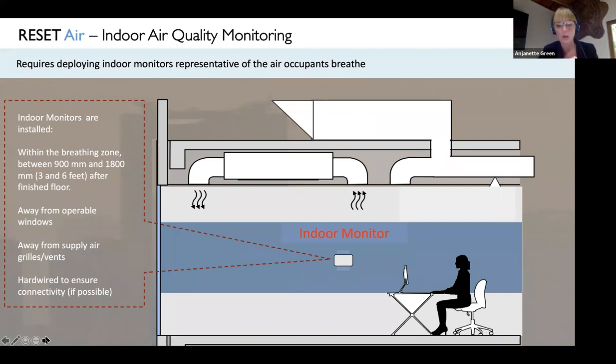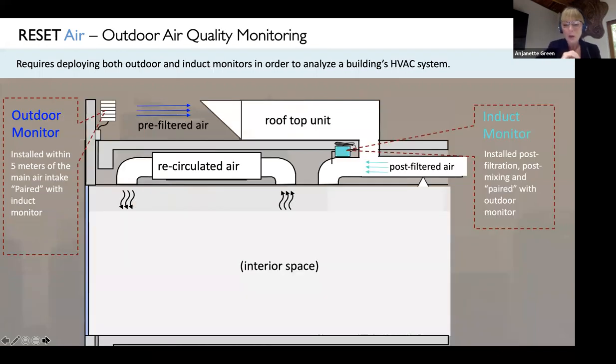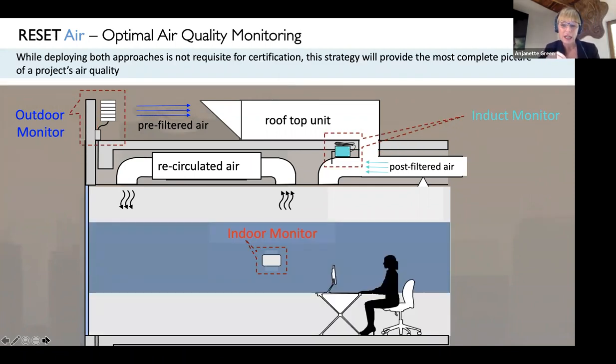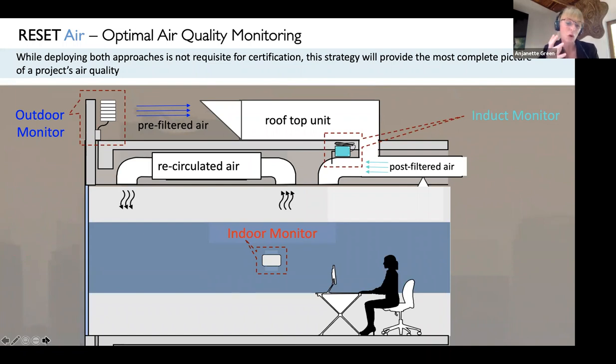The second approach is outdoor monitoring, which requires outdoor air quality monitors to set a baseline, plus in-duct monitors placed after filtration so a direct comparison can be derived. This performance determines if your HVAC system is doing what it should — filtering the air, mixing it properly, and delivering great air to occupants. Deploying both approaches enables you to decouple the data coming from indoor air from the building itself, reducing finger-pointing and helping identify sources of air quality problems so you can remediate them.